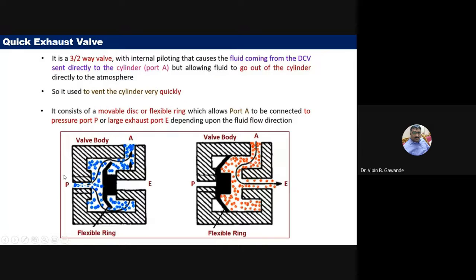In initial conditions, pressurized air flows from the pressure port P to port A connected to the cylinder, and the exhaust port E is closed. When we no longer need to supply air from the pressure port, air returning from the actuator is exhausted directly through port E to the environment.